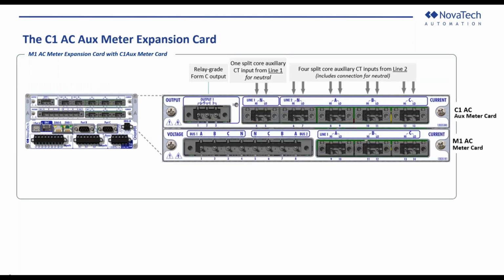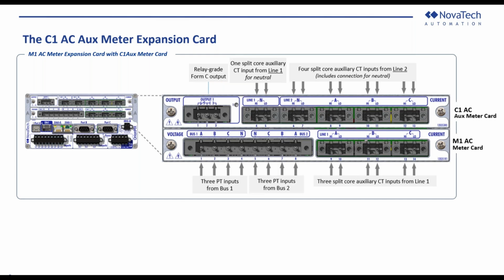Bring in the C1 card. C1 card was developed to bring additional measured quantities into the system, notably a measured neutral from line 1 and also a measured neutral from line 2, along with the phase ABC amps coming in on split core for line 2. So what you see there gives you a full set of measurements, ABC and neutral on your currents, ABC on your potentials. And there is an additional output on there. That's for future use. We see some future higher speed control applications where the output will need to be closed, typically for breaker operation, in response to some changing AC analog input condition, like frequency or synchronicity. But that's for the future.